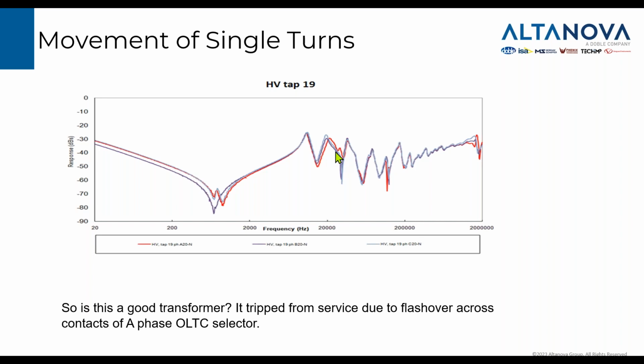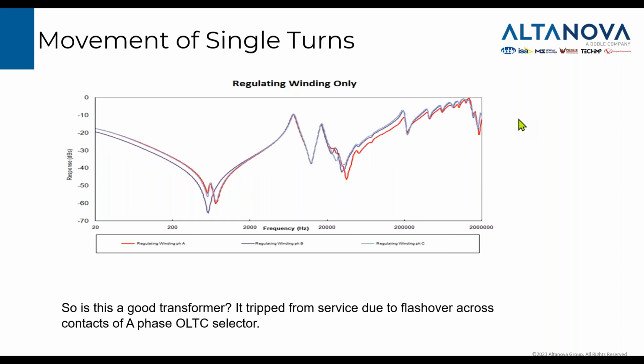Is it enough to say the transformer is deformed? I don't think many people would be that brave to say it's not fit for service, but we had some more options to explore. We tested the regulating winding on its own, and here the difference was more obvious. How did we do the regulating winding only? We did that through the tap changer selector contacts, because they were still open. We had access to them. So we measured the regulating winding, and here the differences are more obvious. Again, phase A. That is in coincidence with previous findings where a flashover on phase A was found and open circuits in that phase.